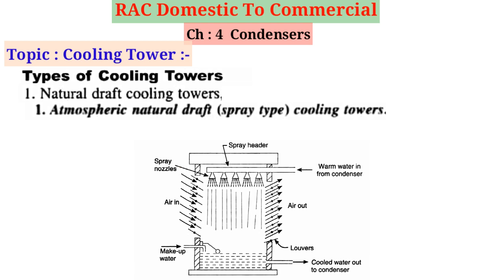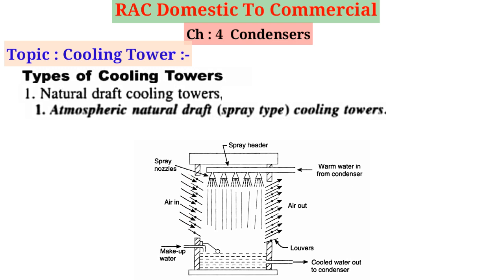The framework and louvers are usually made of steel. The size of the cooling tower depends upon the capacity of the unit. These cooling towers should be located in open space or on the roof of a building, where air can blow freely through the tower. Warm water from the condenser is pumped to a spray header at the top of the tower and sprayed down through nozzles. The heat transfer from water to air is dependent upon the surface of water exposed to the air stream. Therefore, a spray nozzle with a thinner spray pattern is essential for good performance.